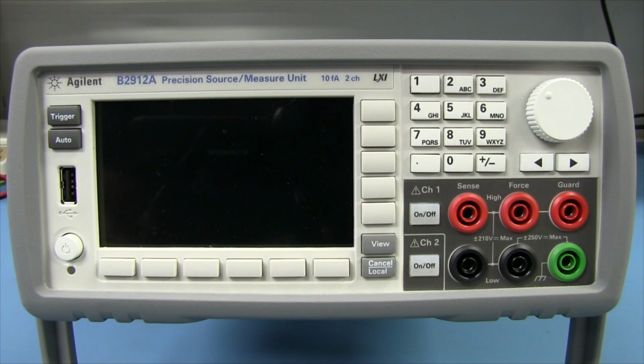So basically what we've got here is 4 precision instruments in one. First of all, it's a precision current source, from 10 femtoamps up to several amps. Also it's a precision voltage source, or precision power supply, anywhere from 100 nanovolts resolution up to a couple hundred volts, depending on the particular model. And it's also got a built-in 6.5 digit voltmeter and current meter to measure all of those ranges. So really precise - we're talking 0.005%, all that sort of stuff. Really high precision, as you'd expect out of a 6.5 digit thing.